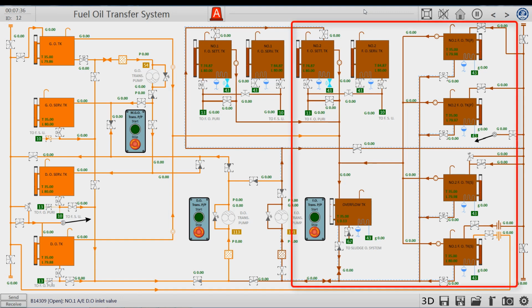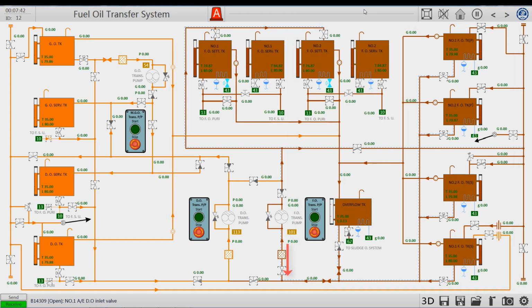The piping arrangement of heavy oil is similar to diesel in principle. The oil tanks connected with the oil pump suction inlet have the fuel oil overflow tank and 4 storage tanks for heavy oil. Through the outlet line above the oil pump, the node has 2 paths. The left pipe connects to the number 1 heavy oil settling tank and number 2 heavy oil settling tank. The right line is connected to the heavy oil filling manifold through this valve, which is similar to the diesel presentation. These are the tanks that can be connected when heavy oil is refueling.